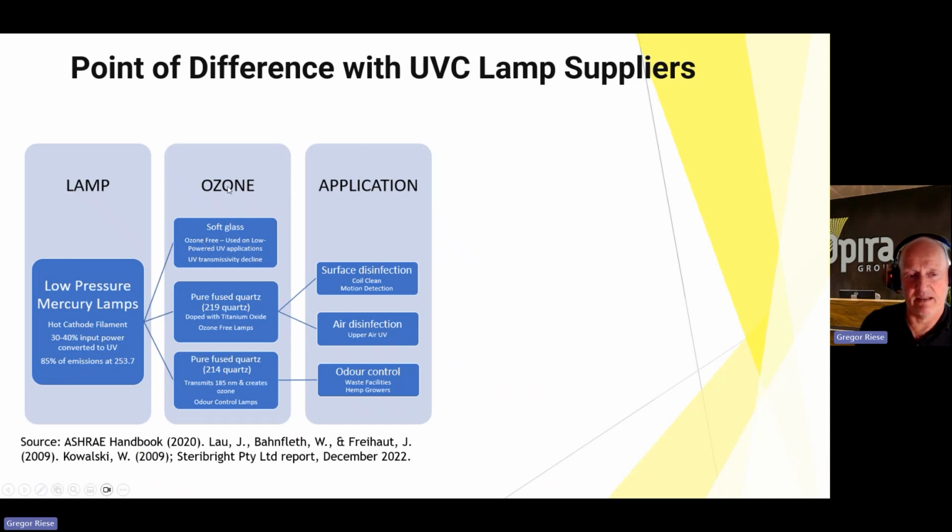There's a bunch of different glasses that can be used, and I won't go into this in any detail, but basically there's a soft glass which is pretty lousy because it actually stops UV transmission pretty quickly. It gets affected by the UV. What's used commonly is pure fused quartz, and there's two different types.